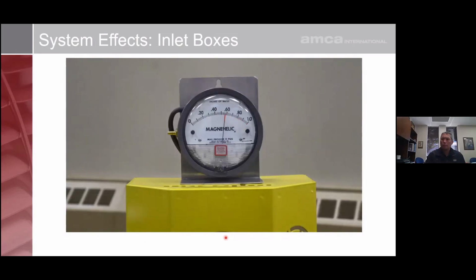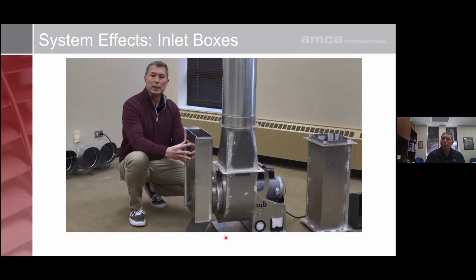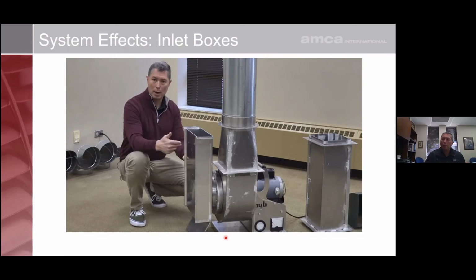Okay. Notice that the fan's doing a couple different things. One is the efficiency, or the amount of pressure that the fan's generating, went down significantly. It's almost half as much as what it was originally. Second thing you'll notice is that the needle is not very stable. It's going up and down. This inlet box has actually put the fan into a surge condition. And those surge conditions on a small fan are pretty bad in that, one, it creates a lot of noise. It goes up and down.